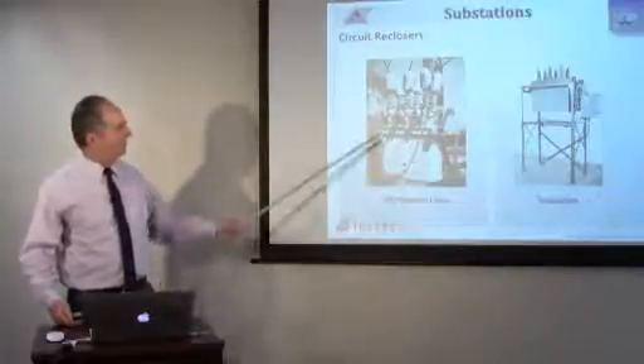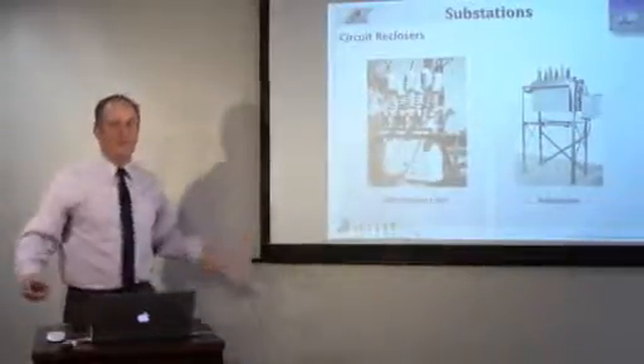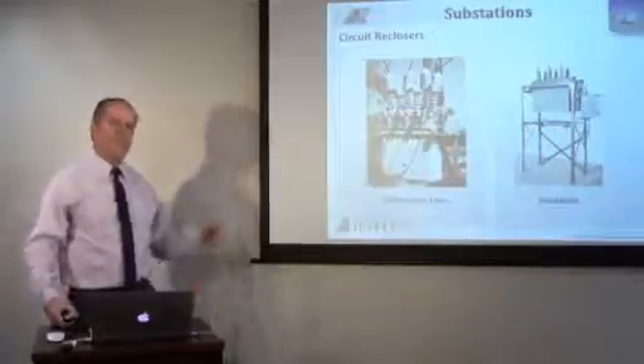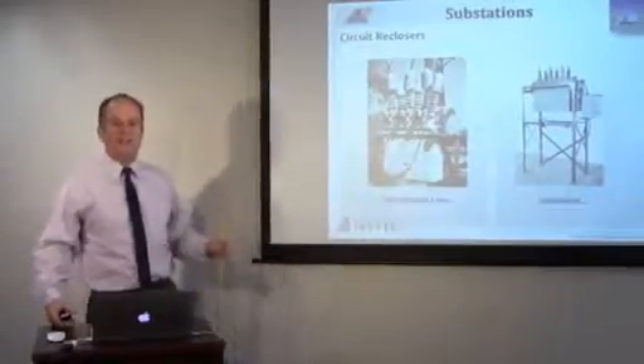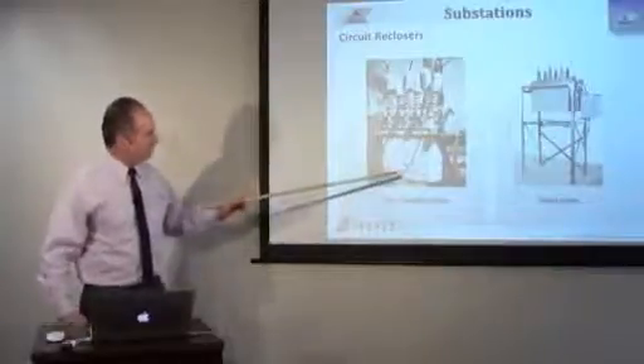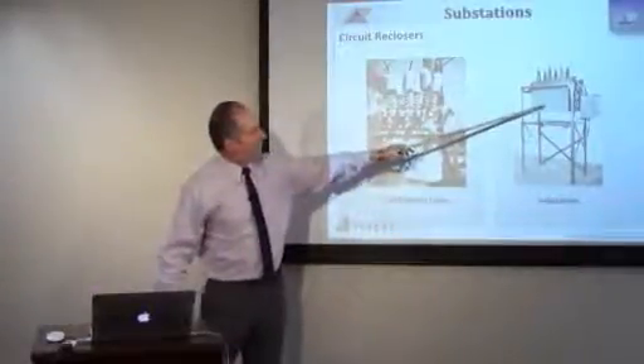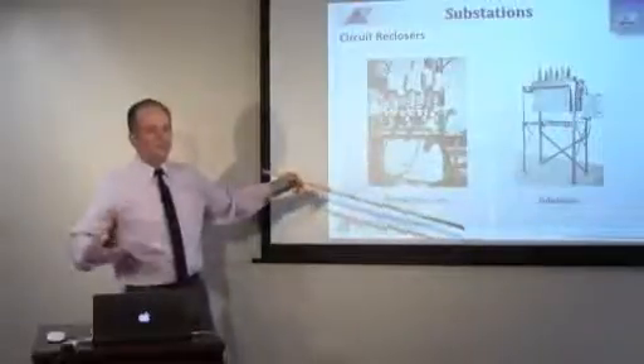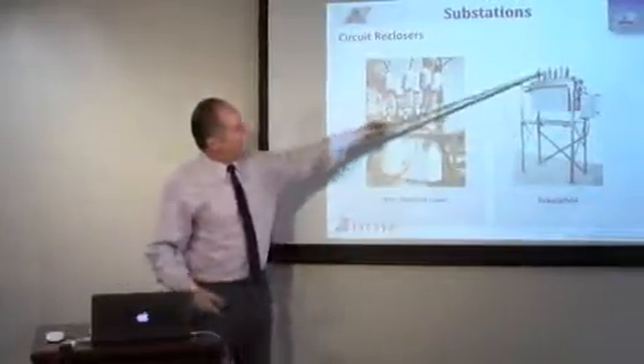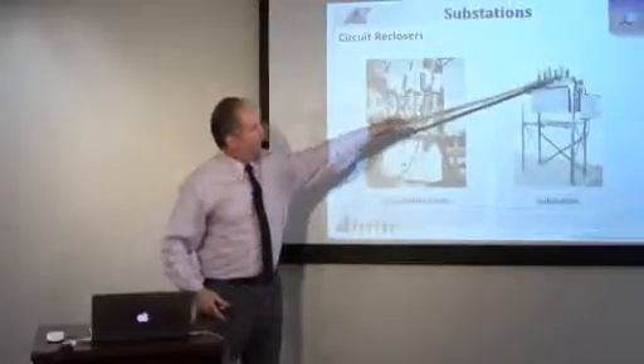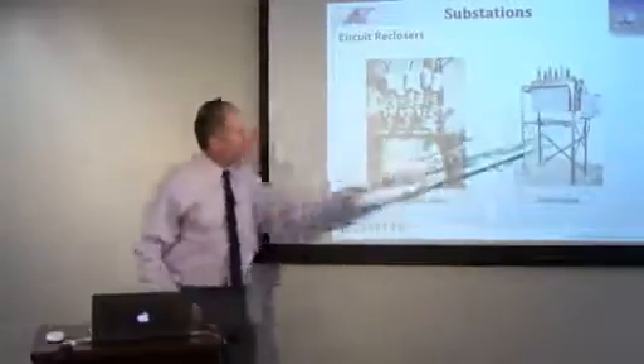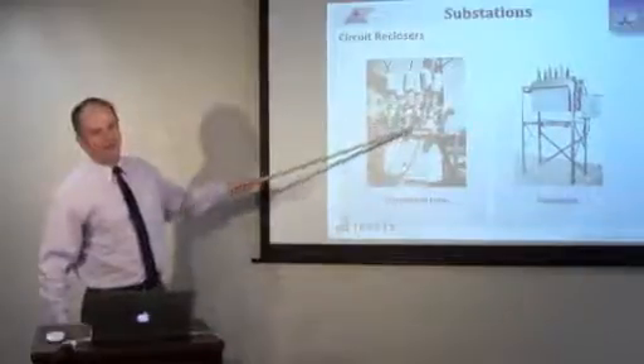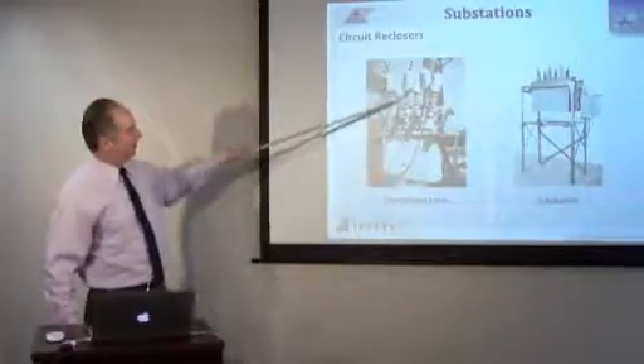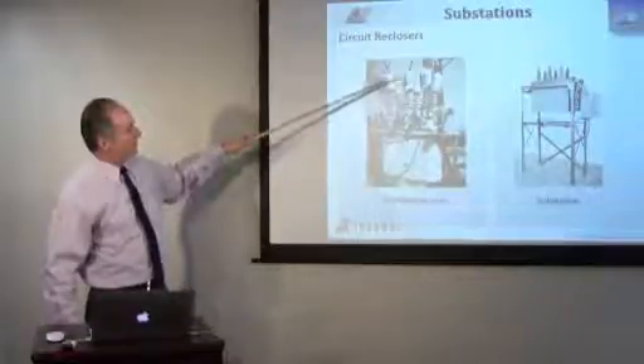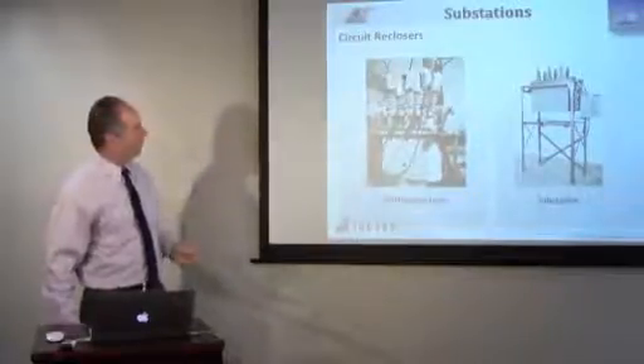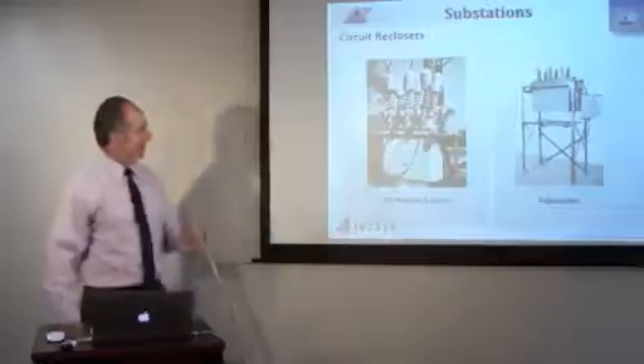What the difference is, they're kind of like circuit breakers, except they have automatic reclosing features, and they have automatic protective relaying schemes inside them. So on distribution, here's a recloser. It's really a circuit breaker with a reclosing feature. Now, 3-phase, the source side and the load side, a control box. Now this one has a lot of bird guards and squirrel guard covers on it, a lot of plastic and rubber over all of it so that there are no exposed wires for squirrels or birds to come in contact with and cause an outage.